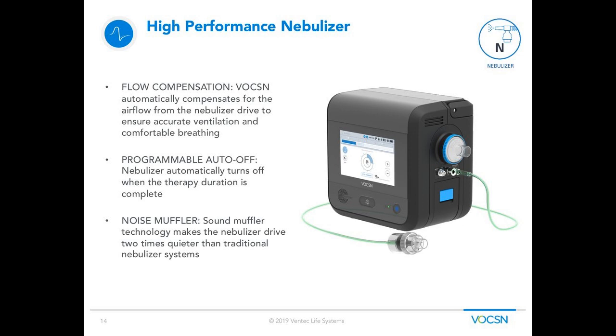Two things happen here. One, if you've ever used a nebulizer before, you know it's a separate device. You have your ventilator, you then have your nebulizer, and you plug the nebulizer in line with the circuit. What does that do for the patient? Well, they get the ventilator, but they also get all the additional flow coming from the nebulizer, so they have this high pressure feeling the entire time during the nebulizer treatment.